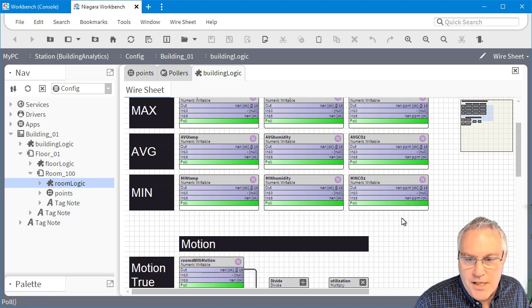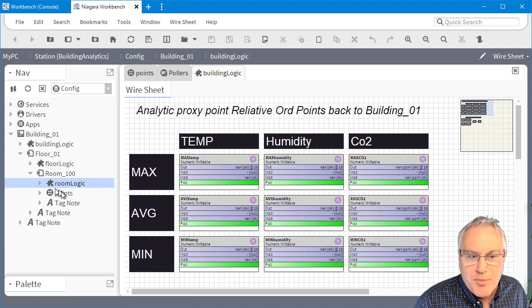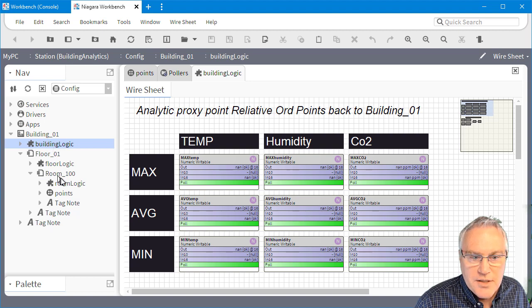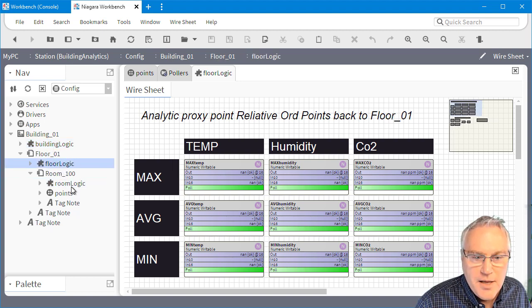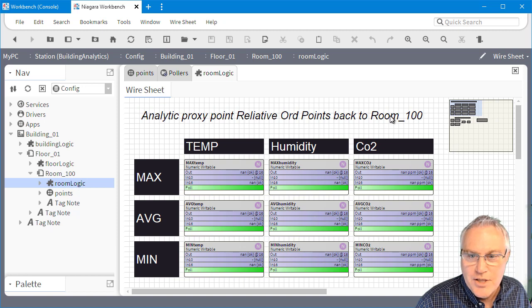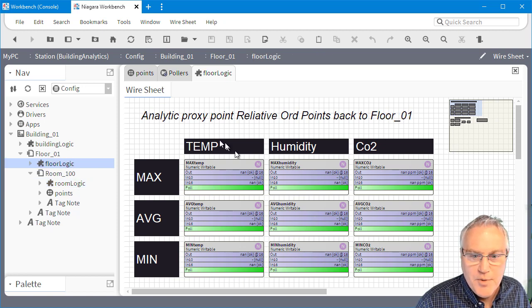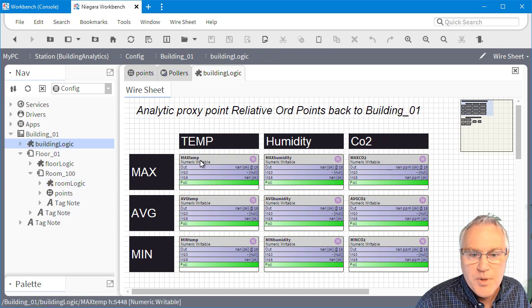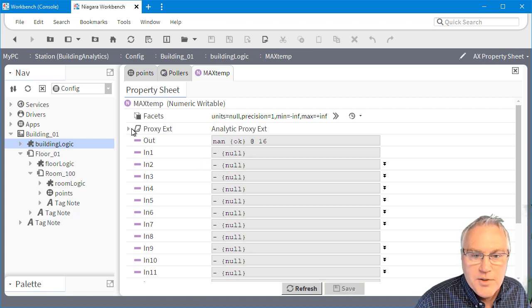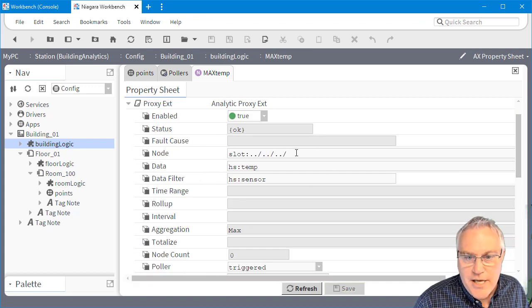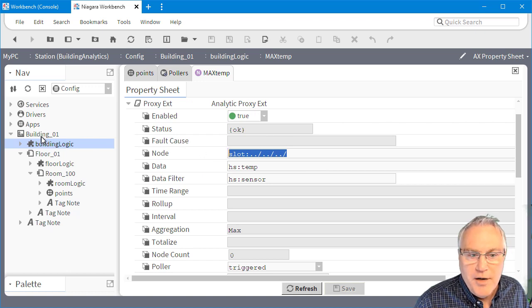Each of these is the same as the previous. So if you look at this, the building logic is the same as the floor logic, the same as the room logic. The only thing I do is I change my notes around just to tell me where I'm going. And how that works is because these proxy points are relative. So essentially this pattern will always go to the node above it. So if you look at node, it's going to go up to building and that's where it's going to start to look.